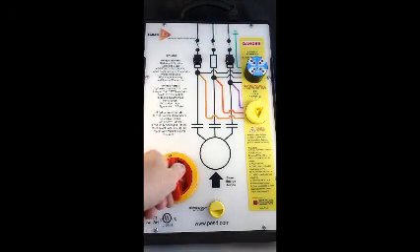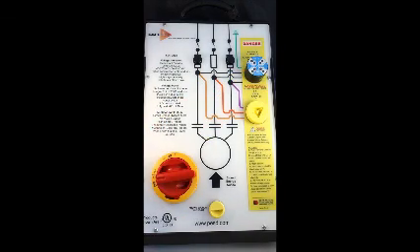As we turn the power off you may notice the LEDs don't go off right away on the voltage indicator. They do not go off till below 40 volt AC, 30 volt DC, so stored energy you can see that in the panel.